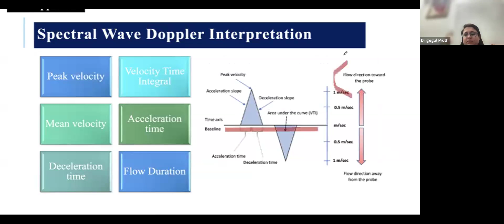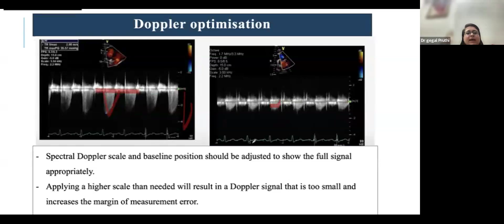In spectral Doppler, this is the baseline and this is the scale. You should remember that the spectral Doppler scale and the baseline position should be adjusted so as to show the full signal appropriately. In image 1, you can see that the jet velocity is very well represented, whereas in figure 2, the jet is very small, which can increase the margin of error during measurement. So we have to adjust the scale also, as applying a higher scale than needed will result in a Doppler signal that is too small, and it will also increase the margin of measurement error.